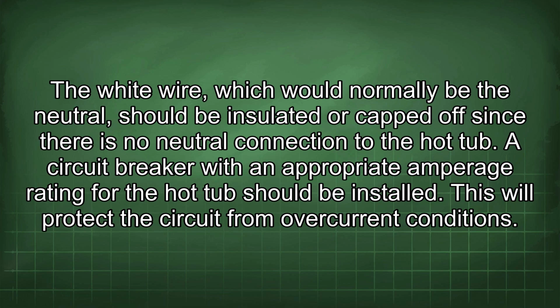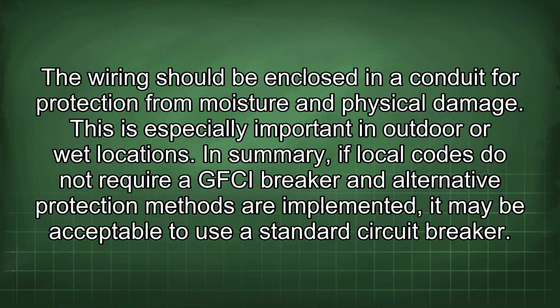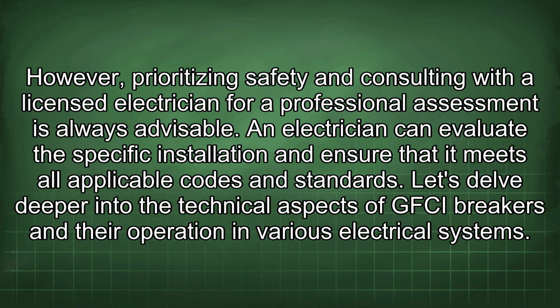A circuit breaker with an appropriate amperage rating for the hot tub should be installed. This will protect the circuit from overcurrent conditions. The wiring should be enclosed in a conduit for protection from moisture and physical damage. This is especially important in outdoor or wet locations. In summary, if local codes do not require a GFCI breaker and alternative protection methods are implemented, it may be acceptable to use a standard circuit breaker. However, prioritizing safety and consulting with a licensed electrician for a professional assessment is always advisable. An electrician can evaluate the specific installation and ensure that it meets all applicable codes and standards.